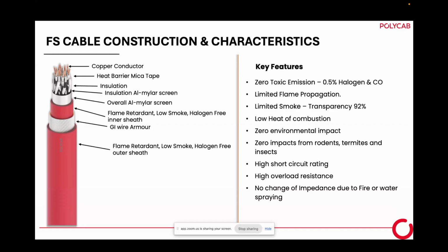So thermosetting polymer means it is a cross-linked polymer. Here in the insulation, we use thermosetting polymer, meaning a cross-linked polymer. So whenever there is a fire, due to heat, it doesn't melt, but it chars. The charring material also acts as an insulation. So this char or ash remains in the position of the insulation and acts as insulation, and therefore the short circuit does not occur immediately.